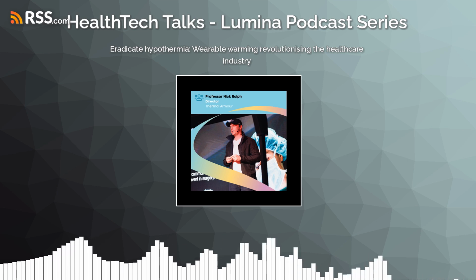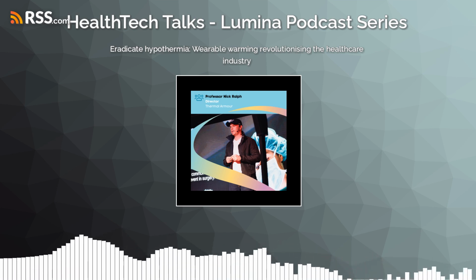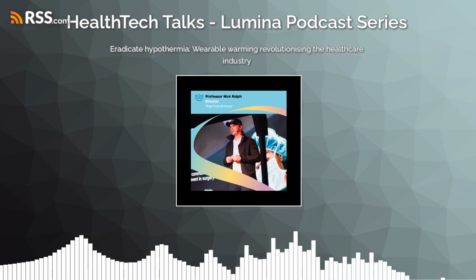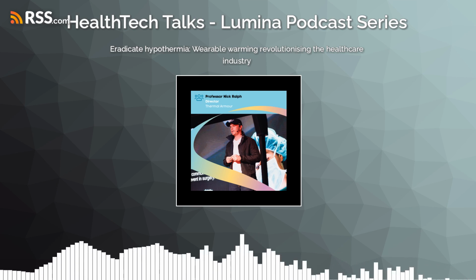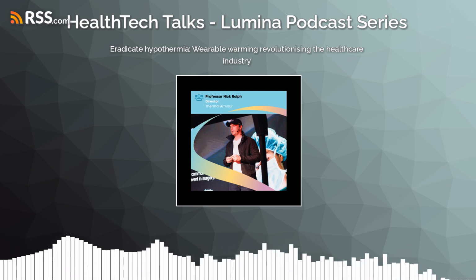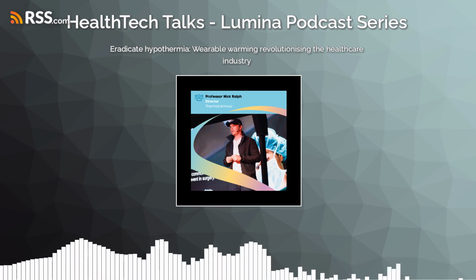And what we see in the global standards, so IEC 60601, is that you only have to hit a maximum. It doesn't actually mean that you have to hit a minimum. So you could actually invent a device that hit 30 degrees and it would actually be compliant. So we see the standards themselves are actually allowing poor competitors onto the market. And so we're going to work in that space to try and tighten up things and perhaps even shrink the market to the few good ones left.